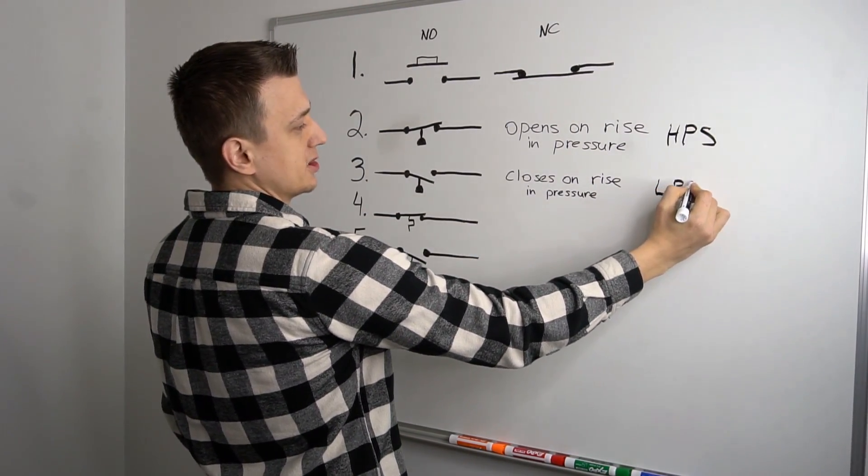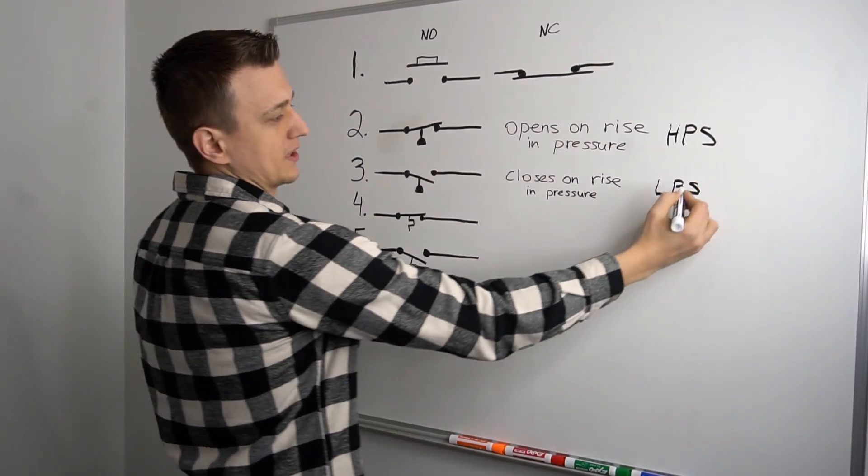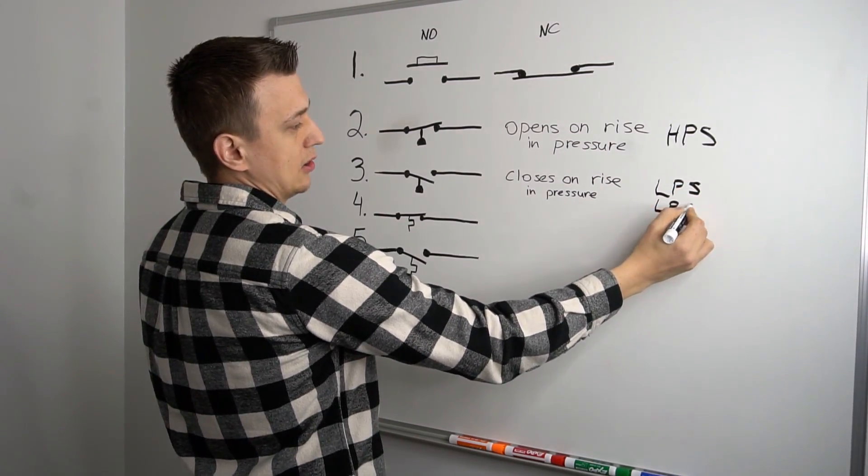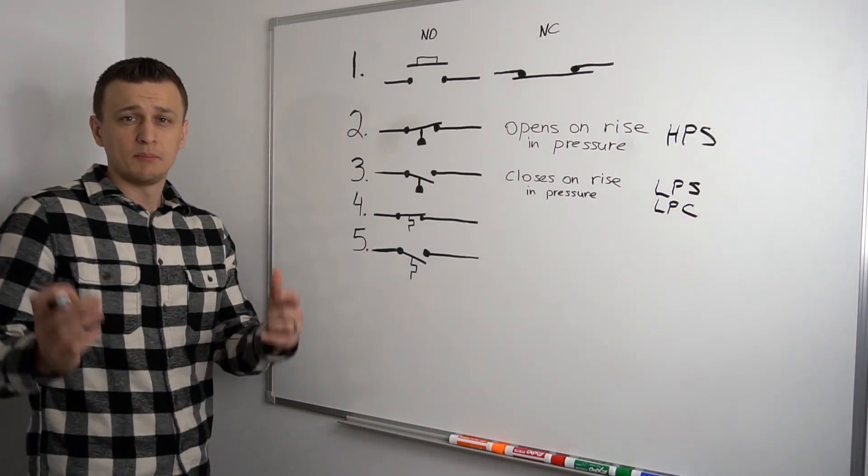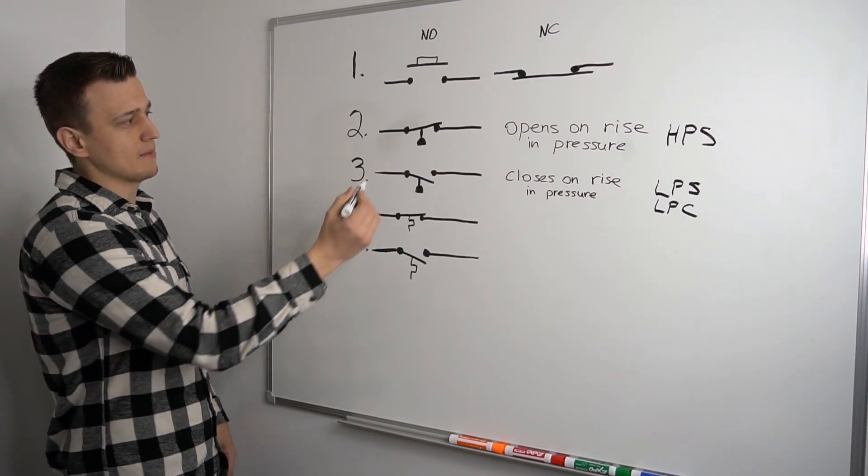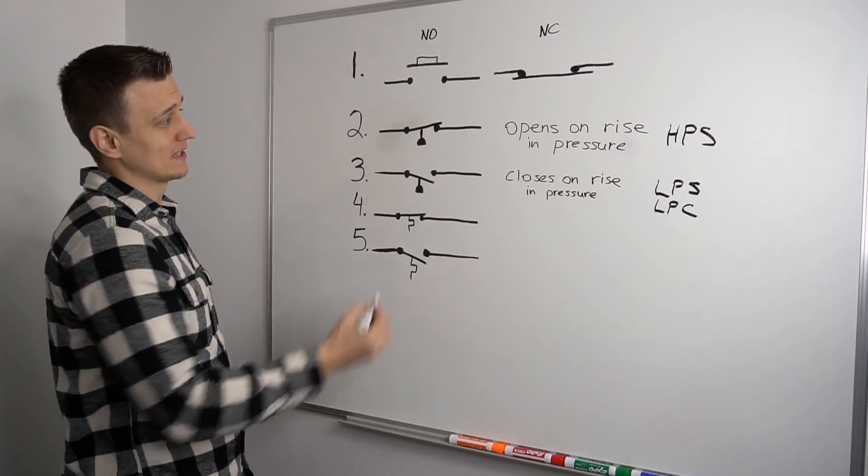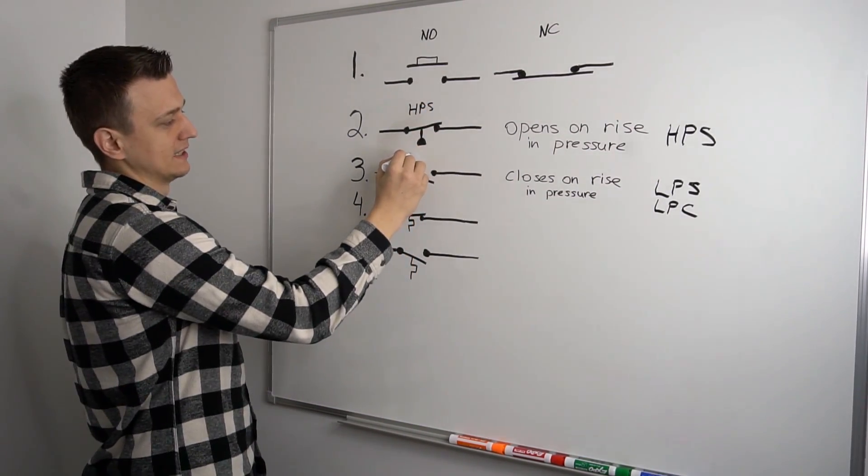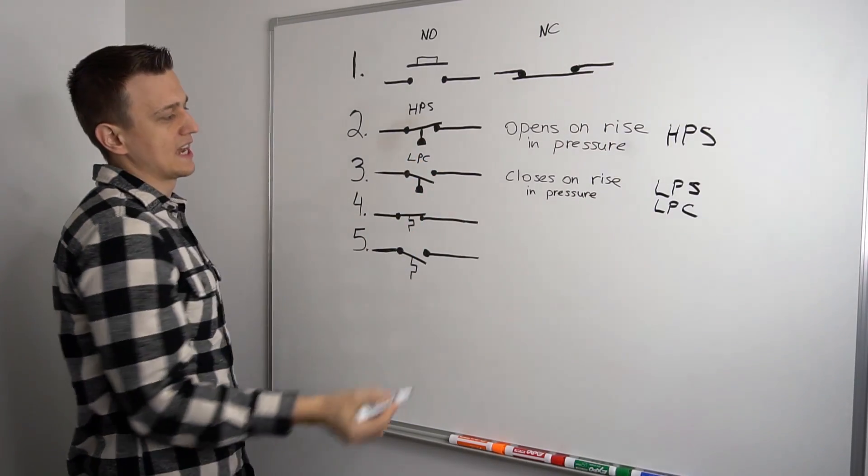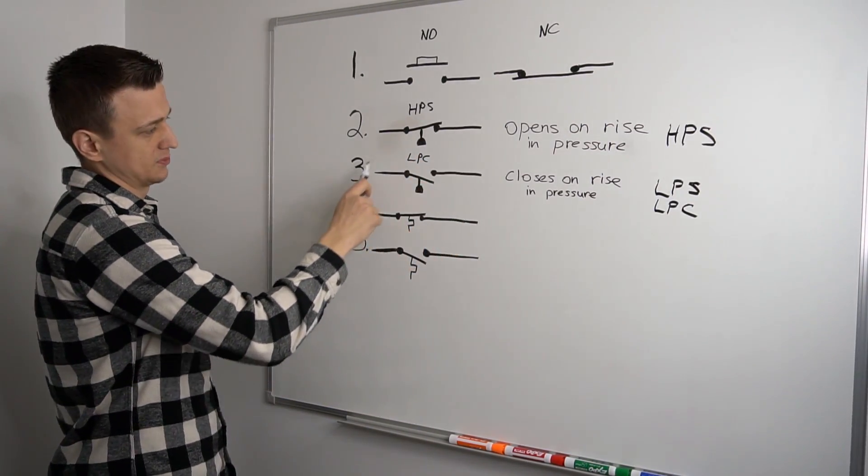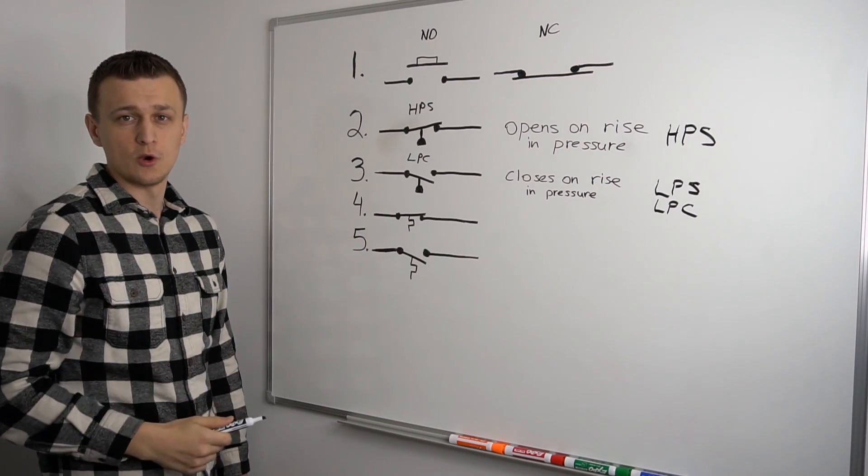So this one would be an HPS for high pressure switch and low pressure switch right here. This is for air conditioning. So this one can be written either as an LPS or LPC, low pressure cutoff. But on most air conditioning wiring diagrams, the good thing about those is that most of the time, these will be labeled anyways. As for furnaces though, furnaces are always going to have this pressure switch right here, which is normally open.